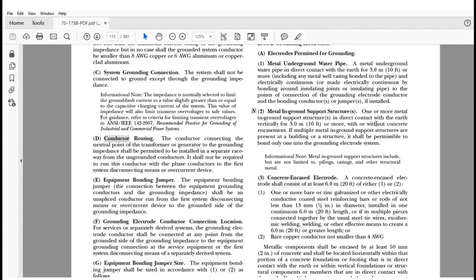And it doesn't matter whether they're in concrete or not, or they're driven piles, steel piles, whatever has been driven down. The application here, based on how it's defined, is the structural metal member of a building or structure needed to be the conducting object with direct contact with the earth. So maybe the pilings or similar objects that are actually driven into the earth, or maybe there's a hole bored into the earth and you have a structural supporting member put down in direct contact with the earth. That's what we're talking about, a metal in-ground support structure.